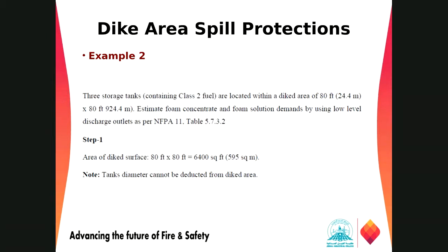Now we have one calculation for the dike area, the protection of the dike area with foam solutions. We have three storage tanks in our dike area. So this is our dike area, and these three storage tanks need to be protected with the foam solutions. So we have to calculate the quantity of foam required and the number of monitors.